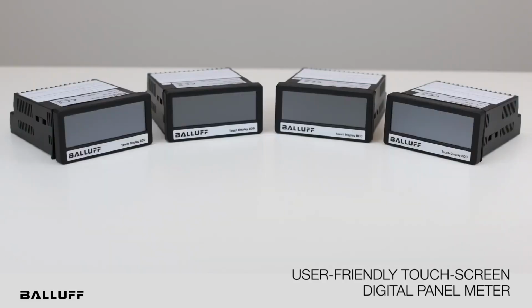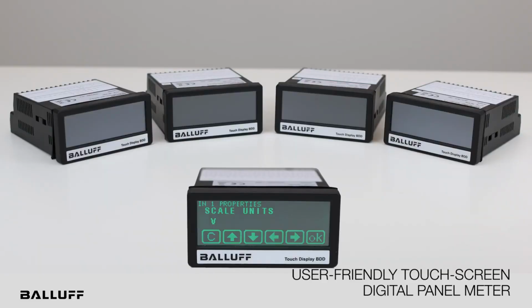Another nice feature is the wide variety of engineering units that can be displayed, eliminating the need to create a physical label on the panel to indicate units. Some typical units could be volts, amps, millimeters, inches, feet per minute, gallon per minute, degrees Fahrenheit, or degrees Celsius. There's even the option to create a custom 16-character unit.